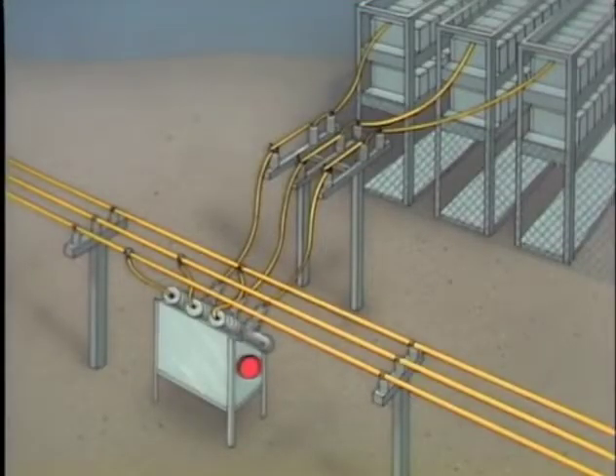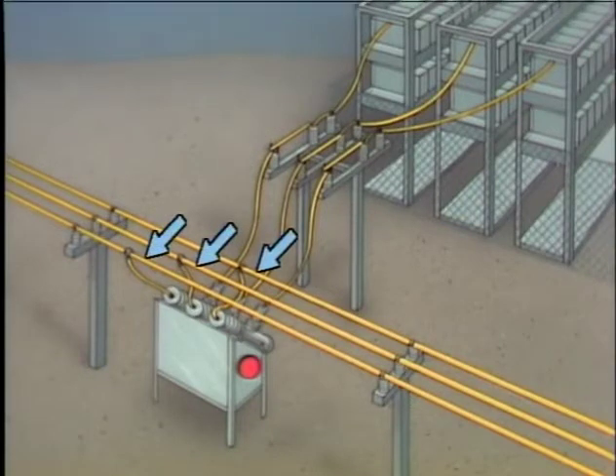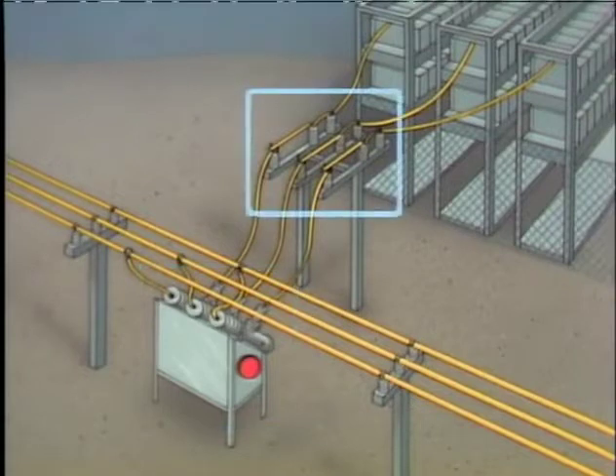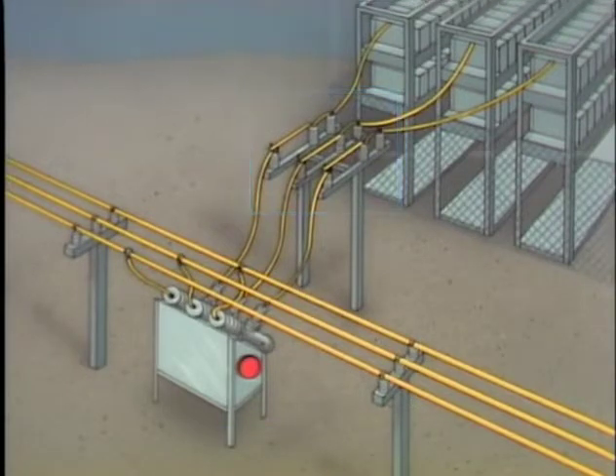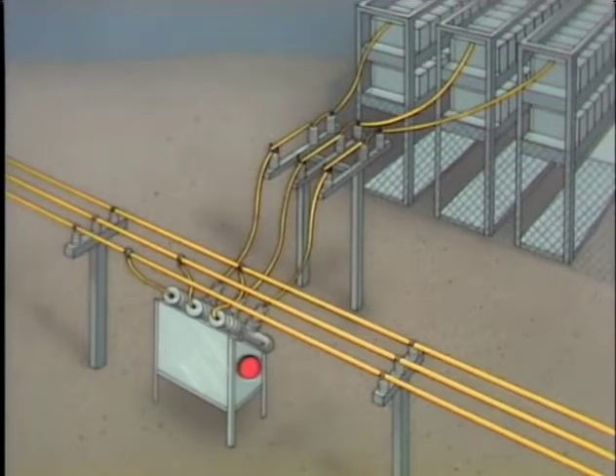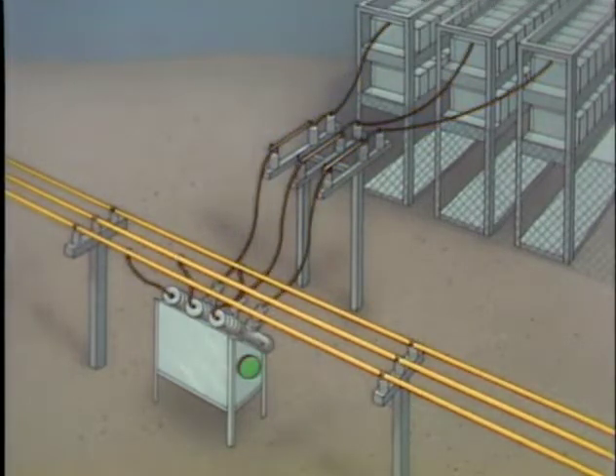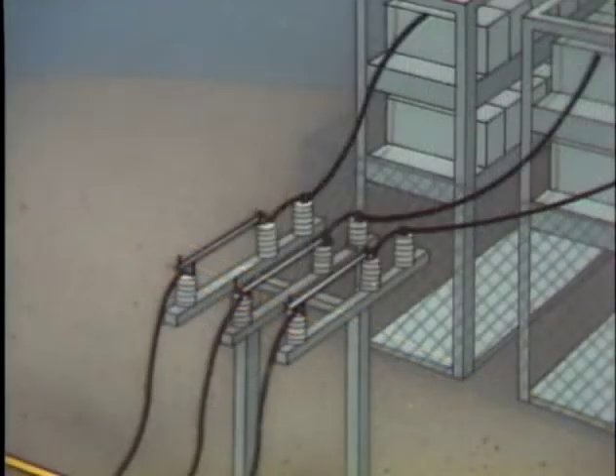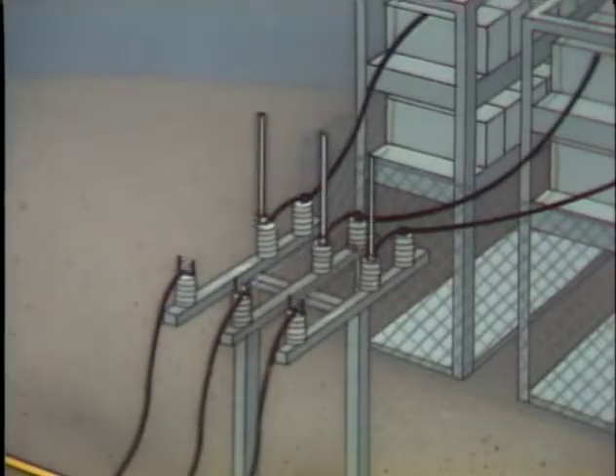This simplified illustration will help show the general principles of de-energizing and isolating a capacitor bank. The illustration includes an energized three-phase bus, a three-phase circuit breaker, three single-phase disconnect switches, and a three-phase capacitor bank. A capacitor bank is de-energized by electrically separating the bank from its source of energy — in this example, by opening the circuit breaker. A capacitor bank is isolated by physically separating it from its source of energy. In this example, three single-phase disconnects are opened to provide a visible break between the source and the bank.